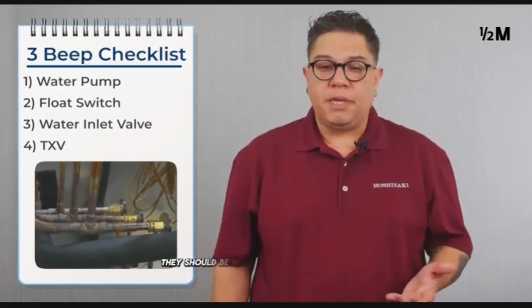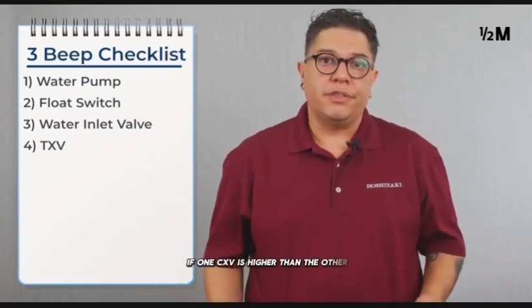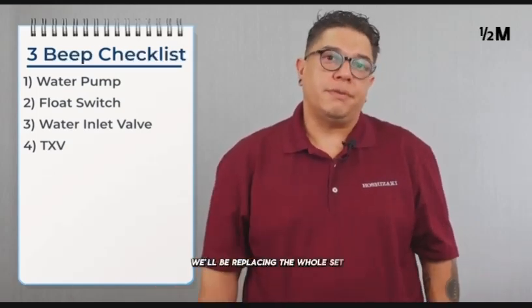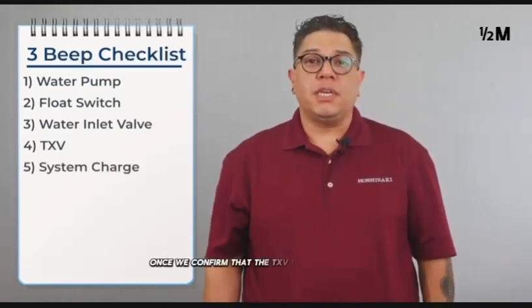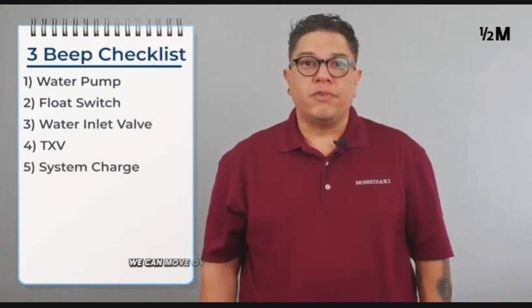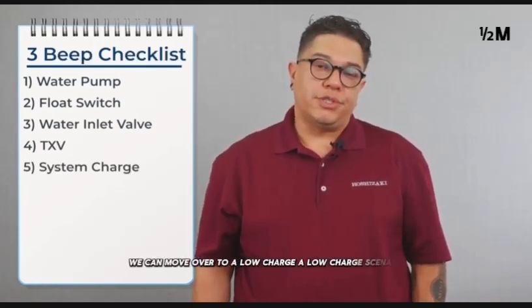With machines that are a little bit bigger, that have multiple TXVs, it's a little bit easier. We're going to do a temperature check on the outlet of the TXVs going to the evaporator. They should be within 2 degrees of each other. If one TXV is higher than the other, we'll be replacing the whole set. Once we confirm that the TXV is working properly, we can move over to a low charge scenario.